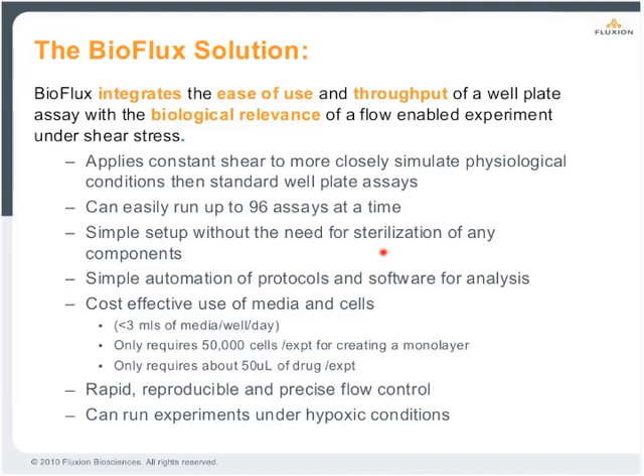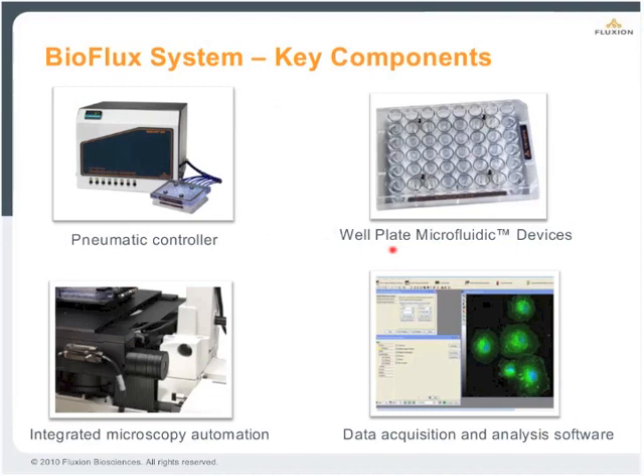At the heart of the BioFlux hardware is the pneumatic controller, which you can see on the upper left side. This affords very tight control of fluid handling, and then the controller is coupled to the well plate using an airtight interface. The data can be collected using microscopy, either manual or automated. User-friendly software enables both seamless data collection with concurrent flow protocols and automated data analysis.